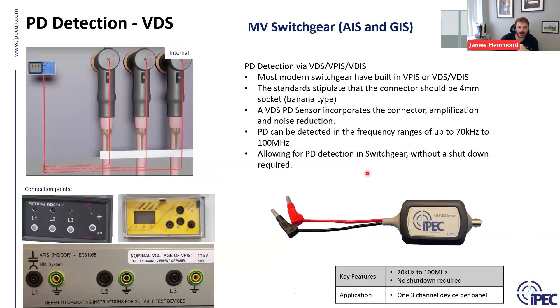And just to give you a quick visualization of what this would look like if you were to see PD being detected, I'll just play these videos. Hopefully you can see the TeV signals placed on the surface of the equipment, and then you get that grouping, as I mentioned at the beginning, of partial discharge patterns. And this is a quick spot test as well.